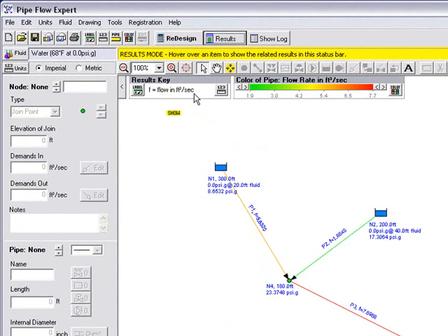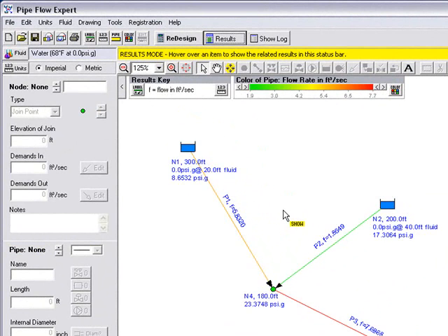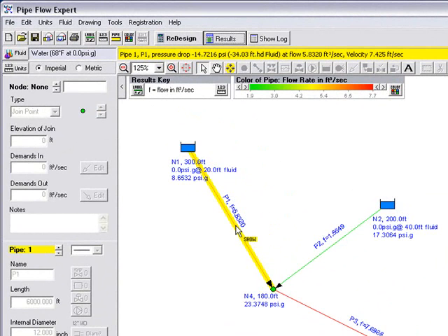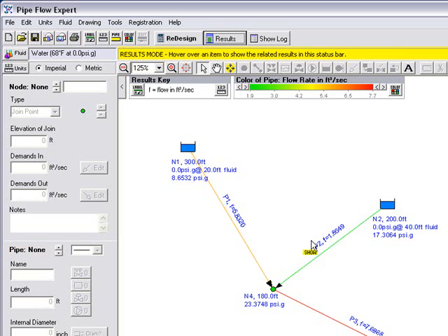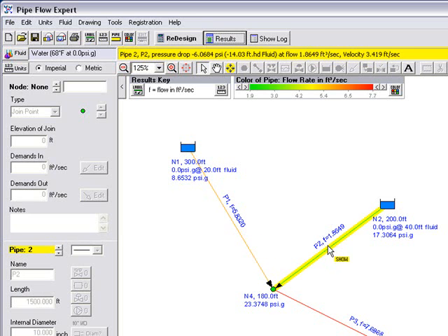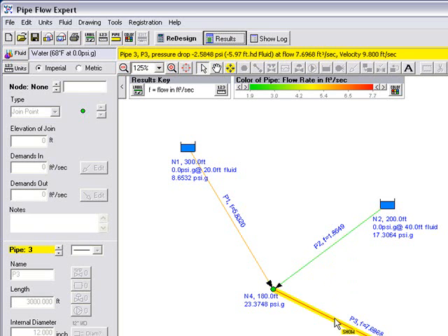The flow is shown in feet cube per second and this information is shown here and we can zoom in to see the data. We can also hover over a pipe and in the yellow status bar at the top of the window we can see the information which gives us a flow of 5.83 feet cube per second. If we hover over pipe 2 we can see the flow that would occur in this pipe, 1.86 feet cube per second and a velocity of 3.419 feet per second. And similarly for pipe 3 we can see the flow and the velocity.